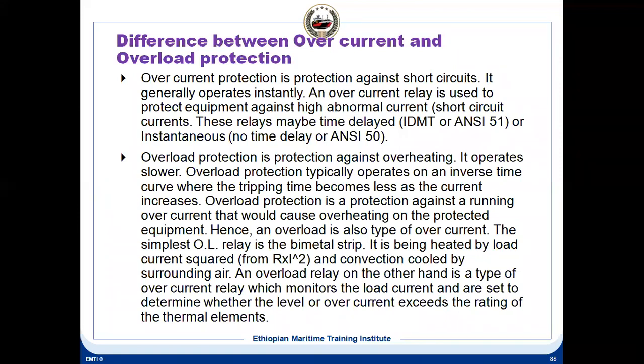It operates slower. Overload protection typically operates on an inverse time curve, where the tripping time becomes less as the current increases. So overload protection is protection against running an overcurrent that could cause overheating of the protected equipment. Hence, the overload is also a type of overcurrent. Simply, an overload relay uses a bimetallic strip, or a thermistor can also be used. It is heated by the load current squared, and convection cooled by the surrounding air.